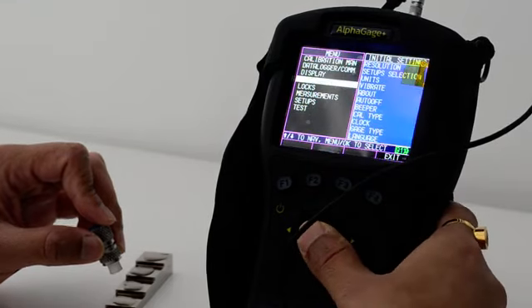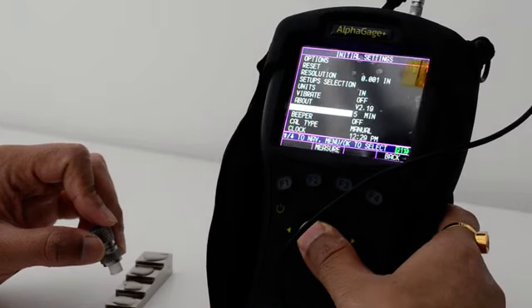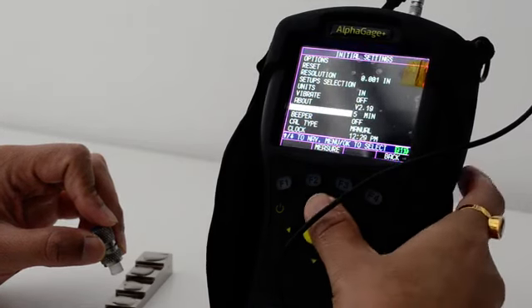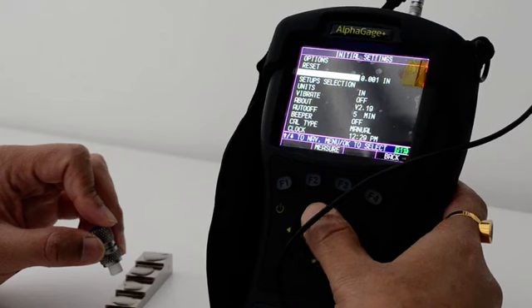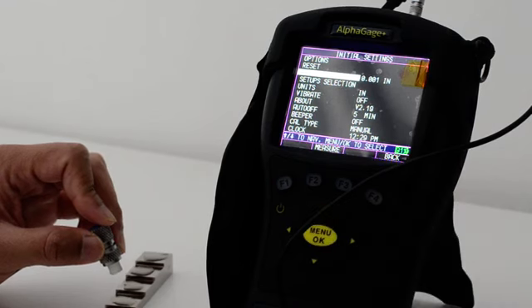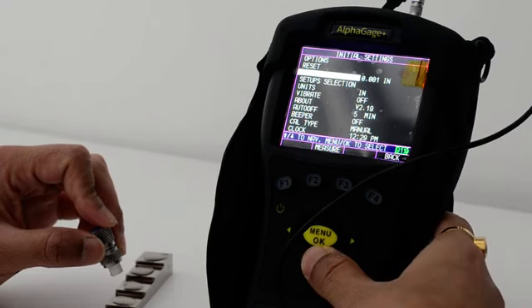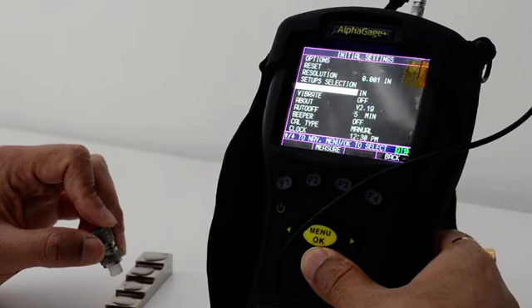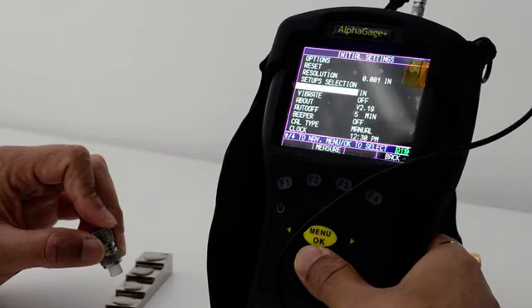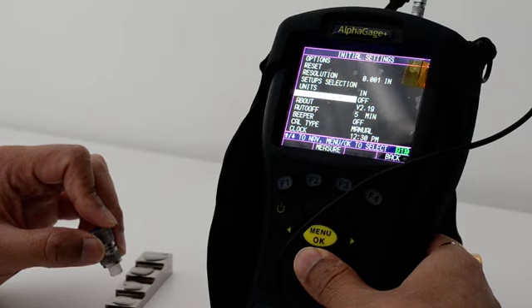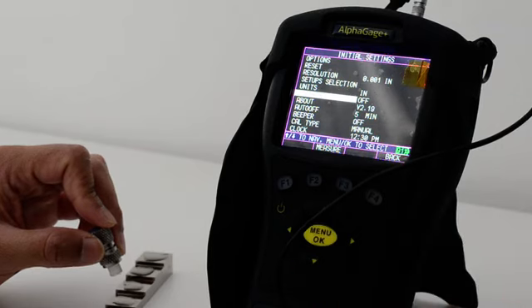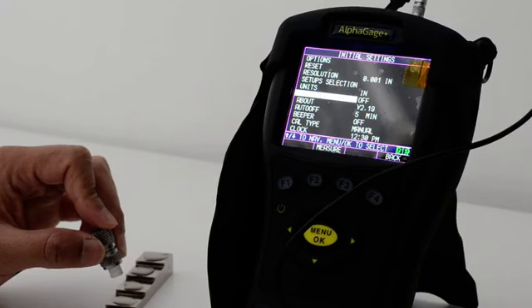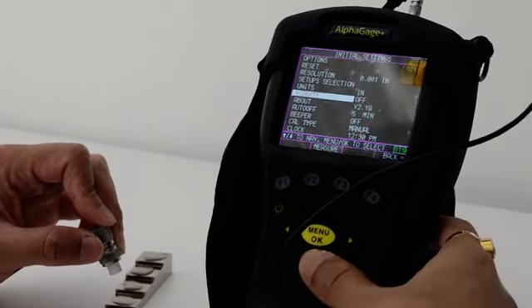And then there are initial settings, where you can do things like change the resolution of your thickness reading from 0.001 to 0.01 or 0.0001. All those things you can do in the resolution section. The units you can change from inches to mm. You can turn on vibration in case you set an alarm, so if something is caught by the alarm, the instrument will vibrate.